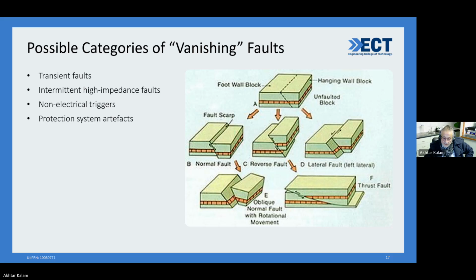So, my friend, let us look at the vanishing fault. And this is my taxonomy that is going to guide my investigation. First thing is transient faults. Transient faults are intermittent in nature. They happen for a very small period of time and cause substantial damage to the system. It could be a high impedance fault, which is intermittent. It could be something non-electrical which has triggered the fault, or it could be power system artifacts. So let us see the transient fault.